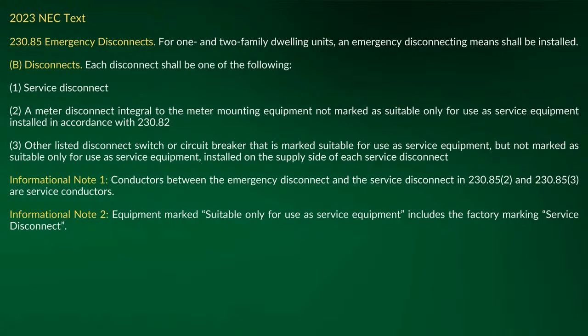And what I like to do is I like to have our service entrance come in, hit a 200 amp disconnect or a 200 amp main breaker. And that's fine. But then what you would have to do in that case, and this is maybe just my opinion and not actual code, which is why I didn't want to jump in last week, because there were so many things going through my head, is you might have to modify that service entrance and put a fuse disconnect and then go over to your transfer switch and then come back to your service entrance point. So it was just really hard for me to comprehend in my head.